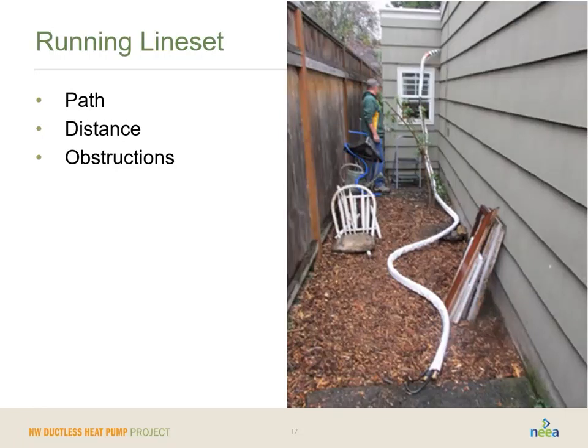Running that line set is going to come with some things you really do need to be thinking about. What is the pathway you're going to use to get from that indoor head to the outdoor compressor? In other words, are you going to have to go through an attic or a crawl space, or can you go directly through the wall as we've seen here? You want to understand the distance to that compressor. Most of these pieces of equipment come with about a 25-foot line set maximum before you have to start weighing in refrigerant. And you can quote me on that to a degree, but please read your manufacturer's specifications. Each manufacturer will be a little different on the appropriate line set before you need to weigh it in. So that distance is important. If you can get within 25 feet, that's going to be really great.